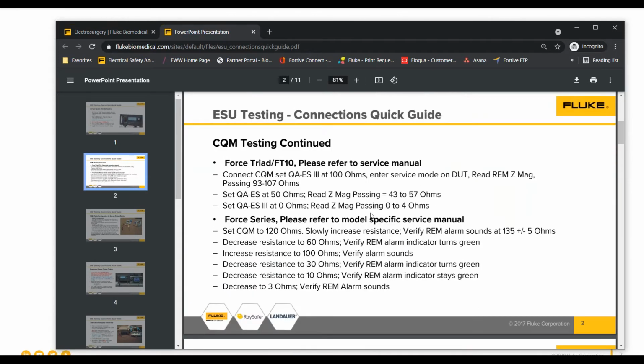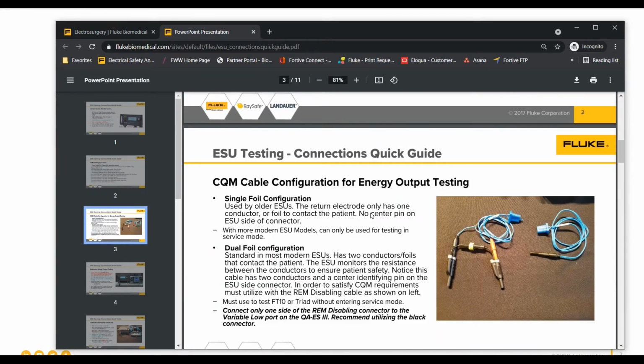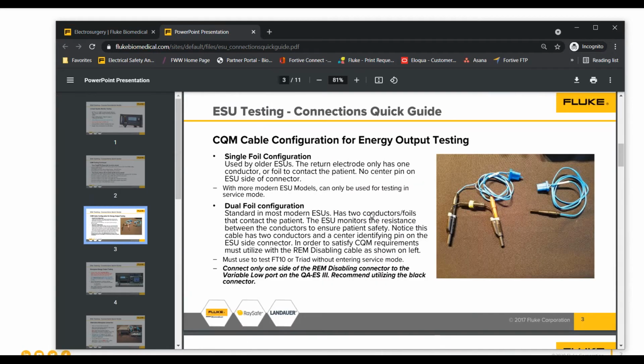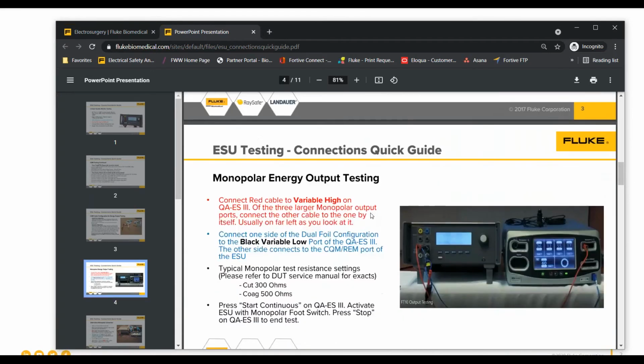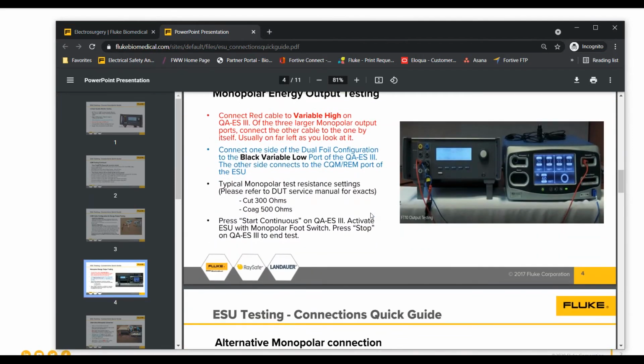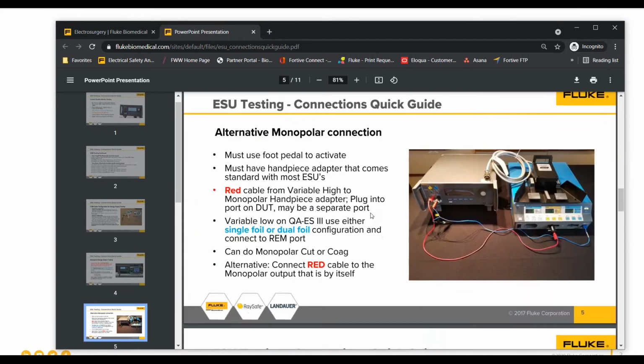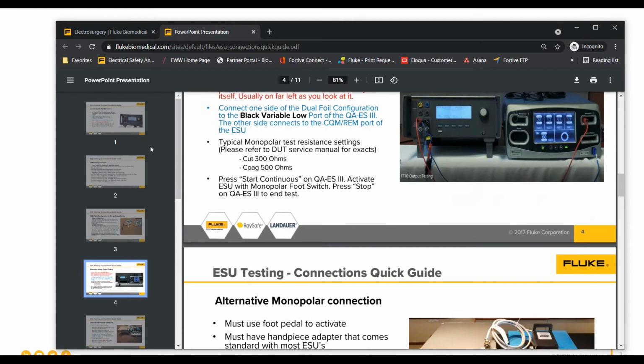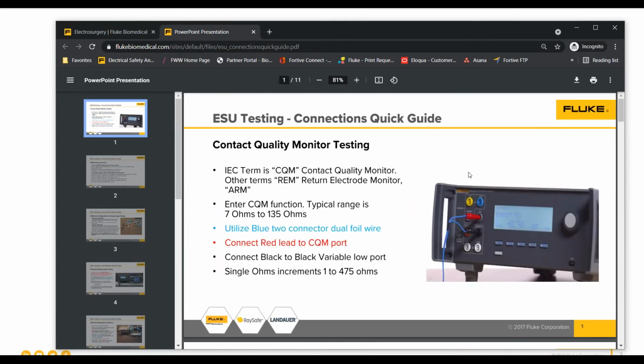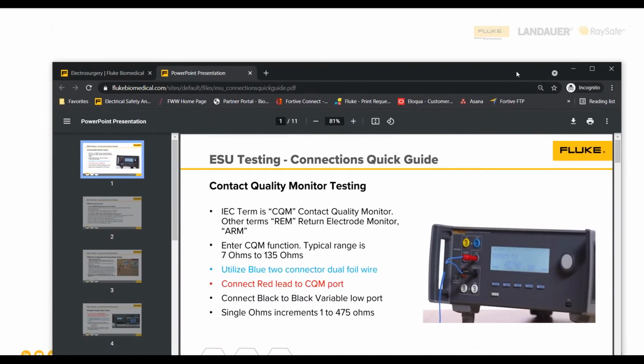I can't emphasize enough, please read your service manuals. You need to find out if there's any special connections, what loads you need to be using, what resistors those loads need to comply with. All that information is there. But here essentially is a really quick guide. Monopolars, monopolars, monopolar. Bipolars, bipolars, bipolar. This will apply to many of the setups. So you can always pull it back up anytime you need it and figure out how to connect your ESU.